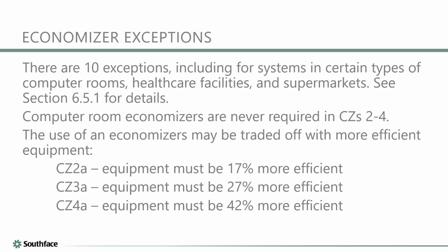One thing I'd like to add is that economizers only pretty much work with rooftop units, whereas a regular split system may or may not be a rooftop configuration. Yeah, I actually ran into that quite a bit, working on some projects in Chicago with some fire stations that all happen to have split systems for the most part, because they have multiple zones for bunkhouses and office area, and then the apparatus bay. So there were a lot of split systems.